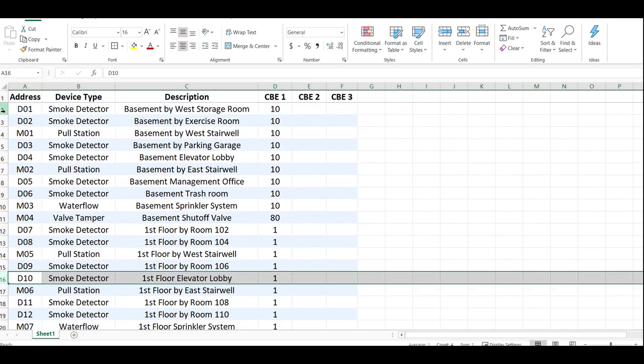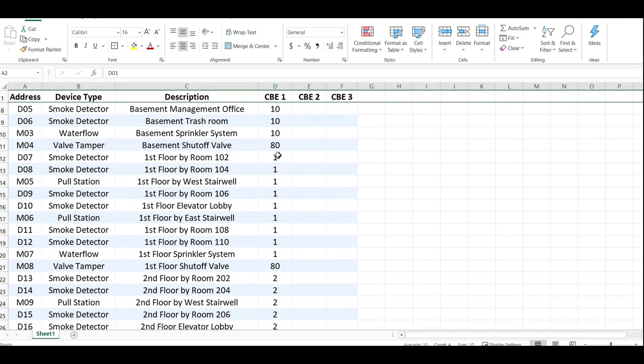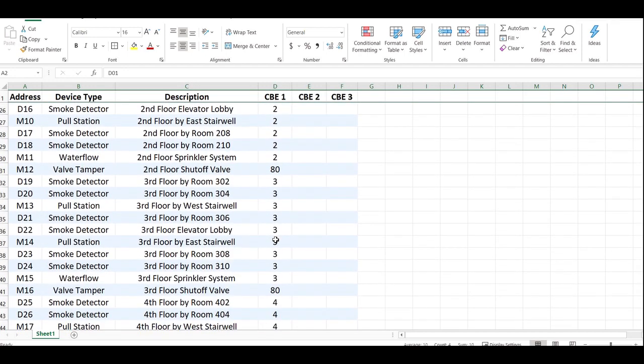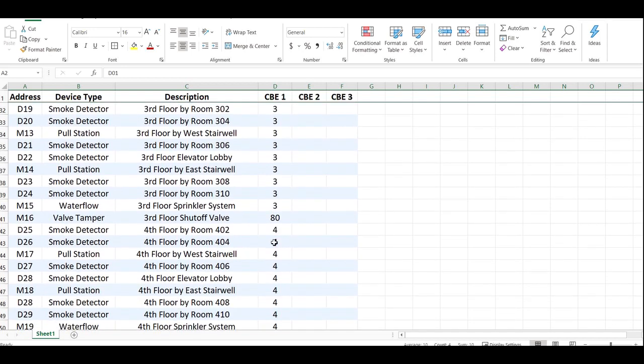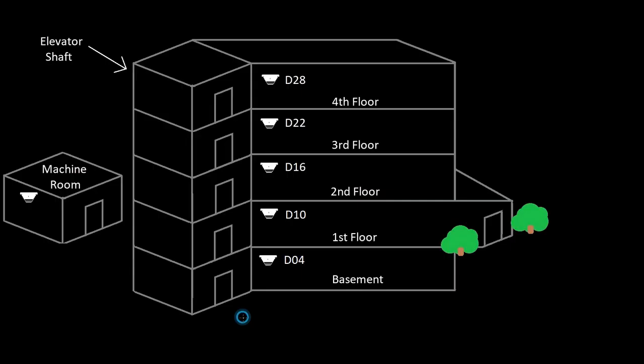You can see there's already some zoning in here. Here's the address scheme all the way on the left and then there's some zoning. It looks like all of the basement is zone 10 except for the valve tamper, all the first floor is zone 1, all the second floor is zone 2, third is zone 3, fourth is zone 4. When we go to do elevator programming now, we only want the smoke detector that's located by the elevator to trigger elevator recall. Now you may find some situations where the recall is actually being done off of a water flow or they want all the detectors in that corridor or something to trigger them.